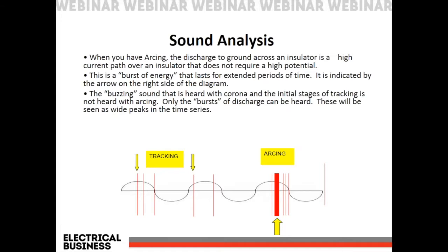Basically, that path does not require high potential. So this is a burst of energy that we can hear, and of course the buzzing sound that we heard, as I mentioned before, with ionization or with corona and tracking, no longer exists now. And all we're hearing now are these violent stops and starts, and they're seen as wide peaks in the time series, and that's why they look like they do.